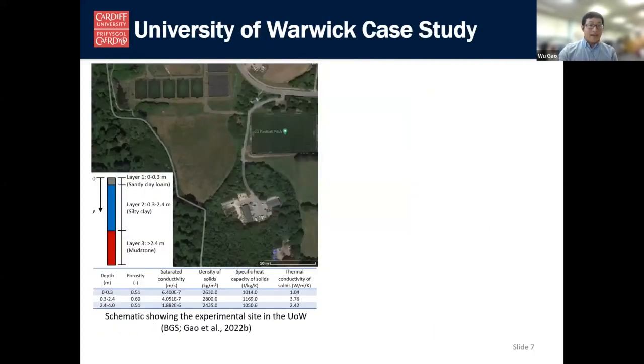We conducted a case study based on an experiment site located on campus of the University of Warwick to investigate the thermal behavior of ground before and after the installation of horizontal ground loops. Based on the borehole data from BGS, the shallow ground is made of 3 layers of soils, and the corresponding soil parameters can be obtained from literature data. 200 U-tube pipes connected in parallel were designed to extract heat and or inject heat into the shallow ground to meet the site thermal demand.